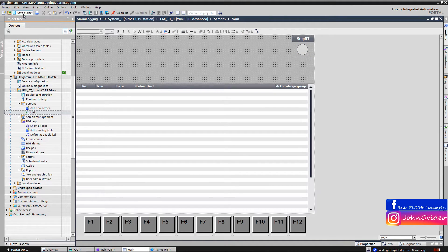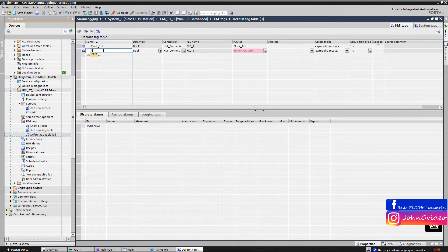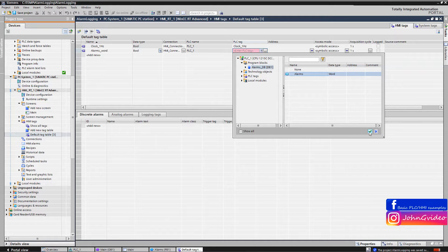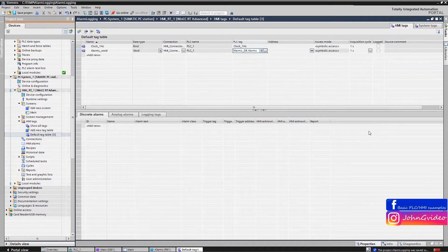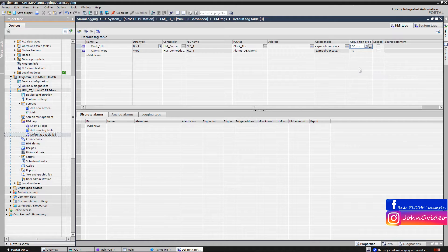We save the project and define a tag with the name 'alarms_word'. We connect this tag to the PLC tag which is situated in our alarms data block. For this we use the connection to the alarms variable, and we also change the acquisition cycle to 100 ms.